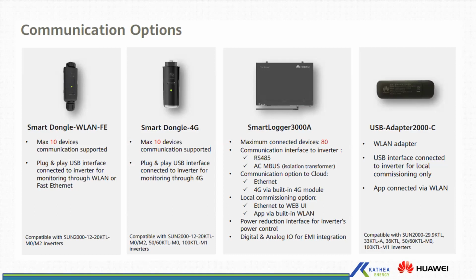And then we have the smart logger 3000. This is the main module for the commercial range. It can connect up to 80 devices, so you can have up to 80 inverters in a chain. So if you are using 100 KTL, it means the smart logger can actually control a plant of up to 8 megawatt. The communication mode has RS485 communication. And then it also uses AC MBUS for isolation transformer.